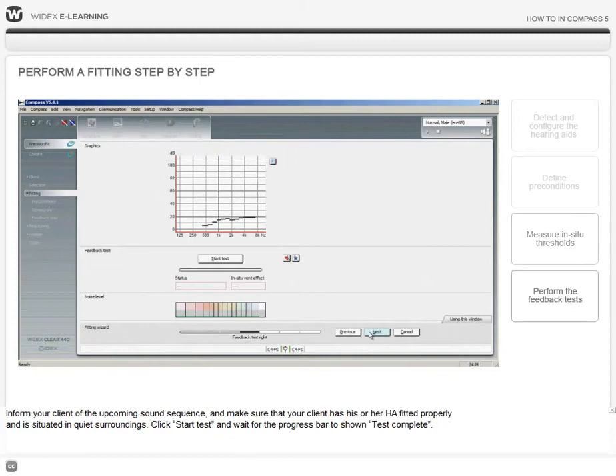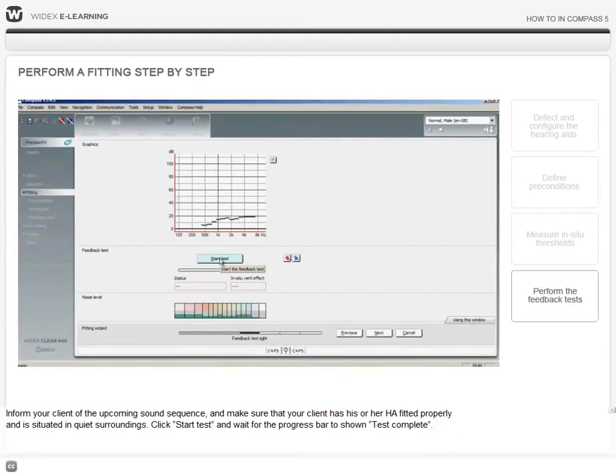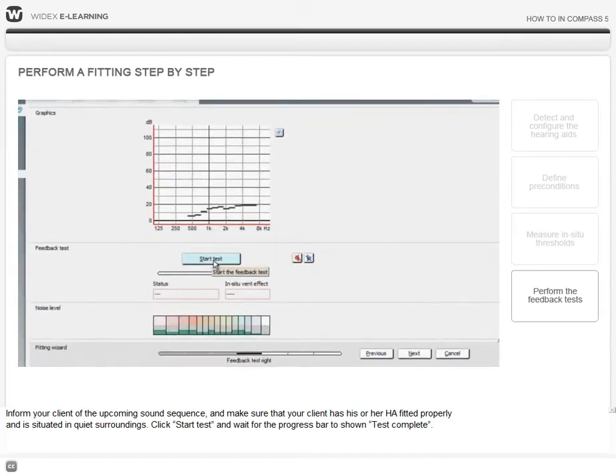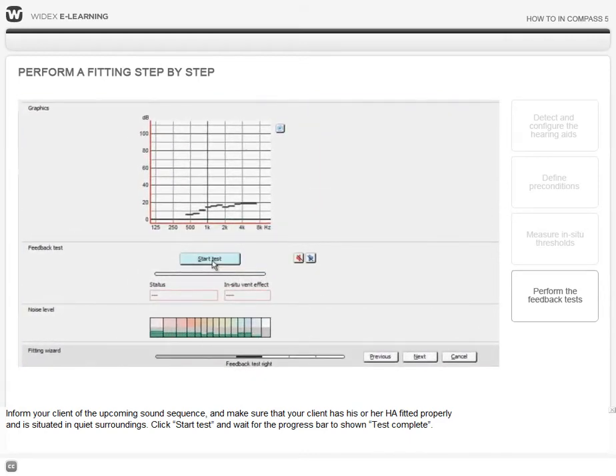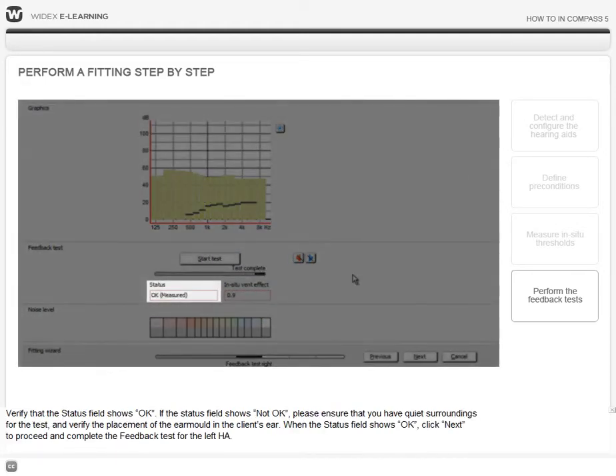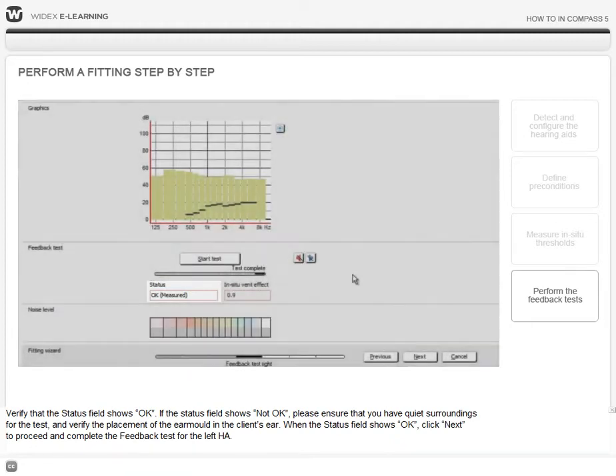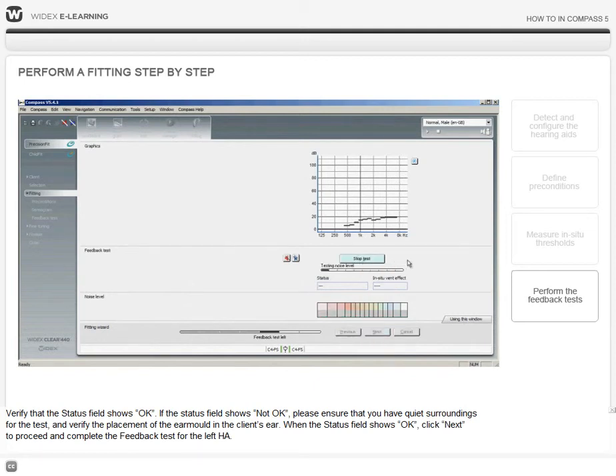aid. Inform your client of the upcoming sound sequence and make sure that your client has his or her hearing aid placed properly in the ear and is situated in quiet surroundings. Click Start Test and wait for the progress bar to show Test Complete. Verify that the status field shows OK. If the status field shows Not OK, please ensure that you have quiet surroundings for the test and verify the placement of the ear mold in the client's ear. When the status field shows OK, click Next to proceed and complete the feedback test for the left hearing aid.